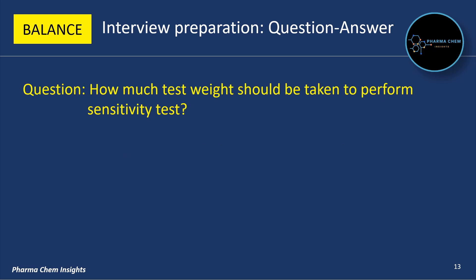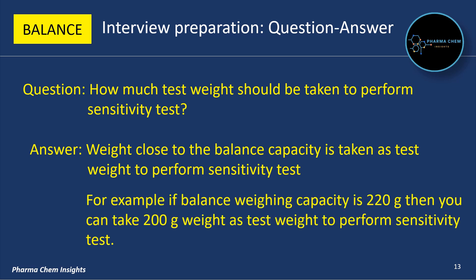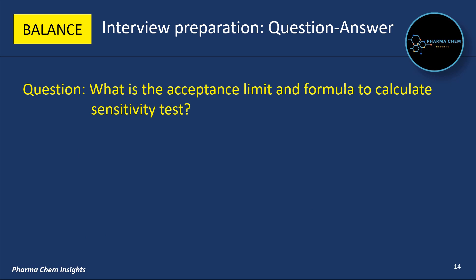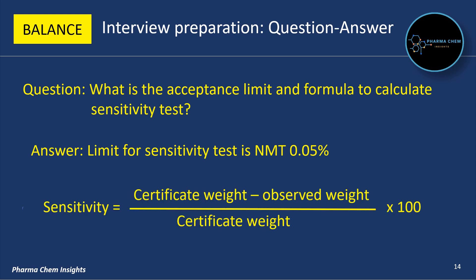Next question: how much test weight should be taken to perform the sensitivity test? A weight close to the balance capacity is taken as the test weight. For example, if the balance weighing capacity is 220 grams, then you can take a 200-gram weight as the test weight. The acceptance limit for the sensitivity test is not more than 0.05%. The formula to calculate sensitivity is: Sensitivity = ((Certificate Weight − Observed Weight) / Certificate Weight) × 100.